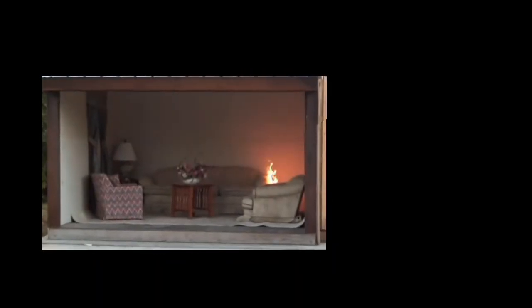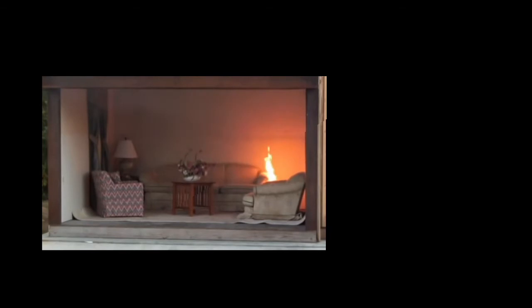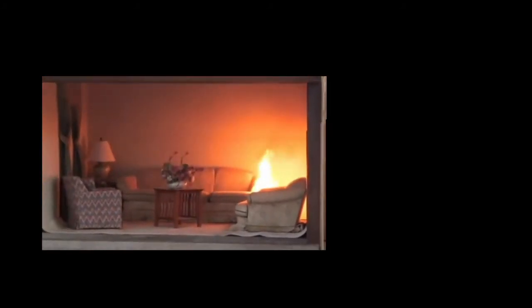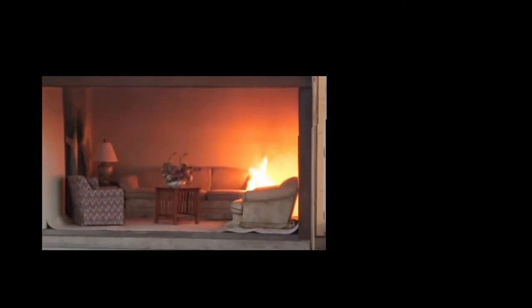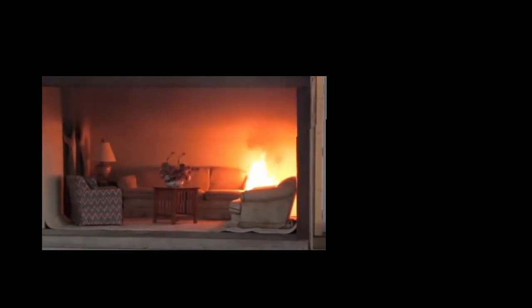Here's an example that takes you to flashover in about 3 minutes. Fire is initiated via a waste basket full of paper. What you'll see is the black smoke at the ceiling. When that forms, you know that there is significant radiation. Radiation goes right through oxygen and nitrogen, the main constituents of air. It's basically transparent.